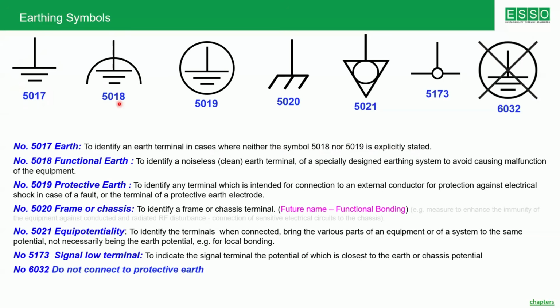5018 is called functional earth, which was also called noiseless or clean earth terminal. 5019 is called protective earth. 5020 is called chassis earth. 5021 is equipotentiality. So like this, multiple applications are required and these are part of the necessary product standard. Sometimes you have biomedical equipment which is not communicating, which doesn't have any electronics. In that case, you need only 5019. If you have another equipment which is working with DC and probably communicating, which has electronics, then you don't need 5019, but you need 5018. So you can find these markings in the respective product standard.